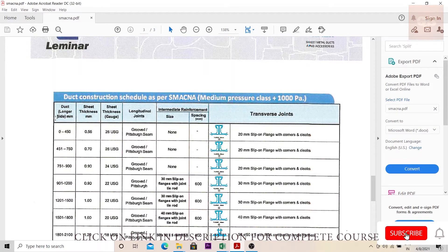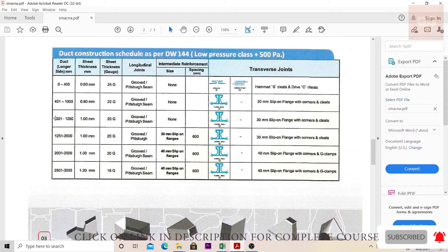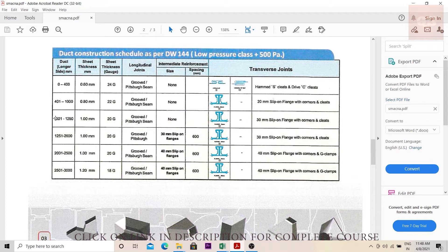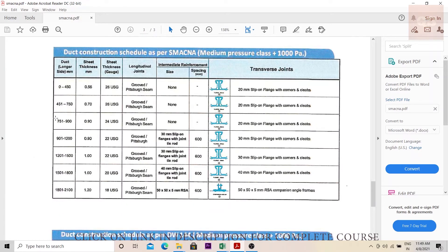The basic factor that differentiates ducts between medium and low pressure class is the fan static pressure and duct velocity. The duct comes under low pressure class if the fan static pressure is less than 750 Pascals and the duct velocity is less than 1500 feet per minute. Medium pressure class applies when fan static pressure is between 750 to 1500 Pascals and duct velocity is more than 1500 but less than 2500 feet per minute.